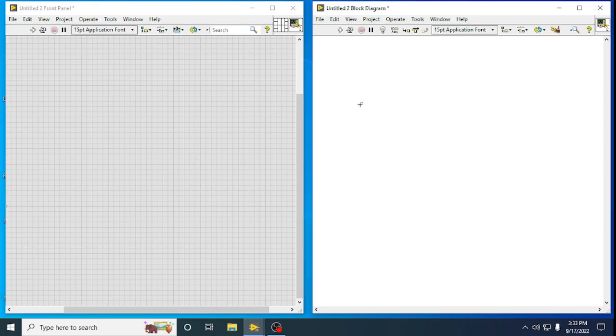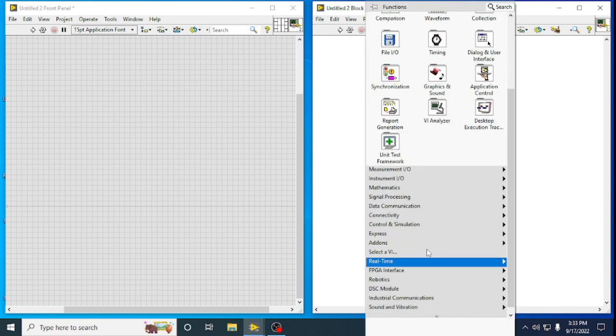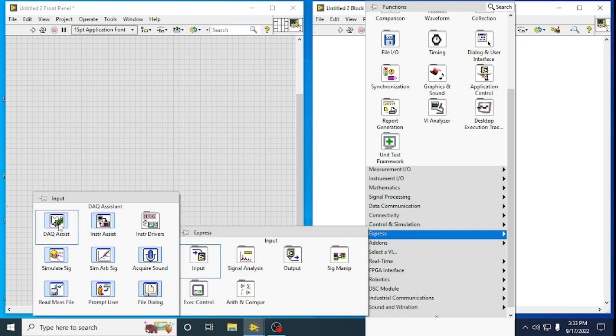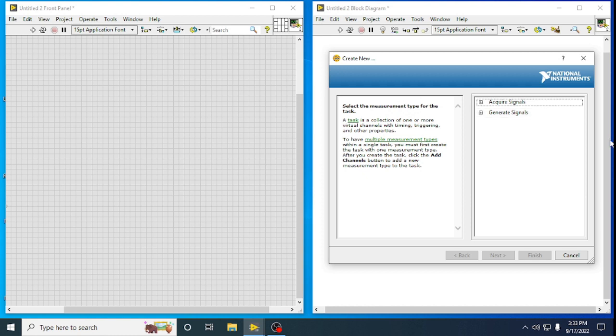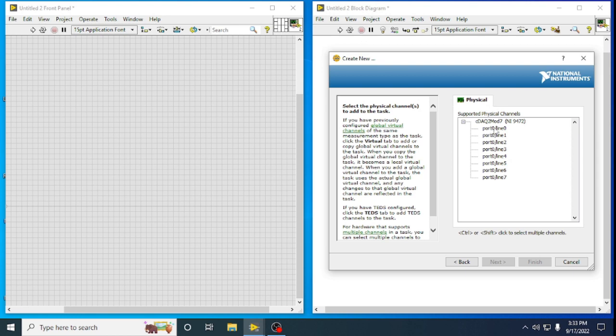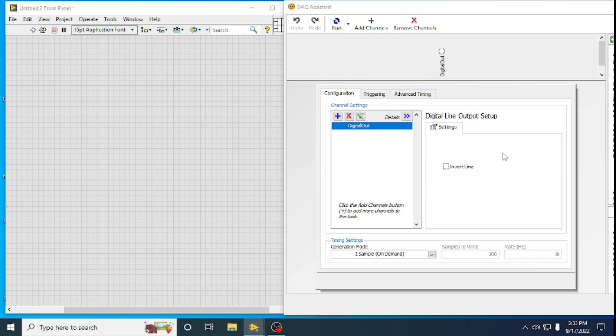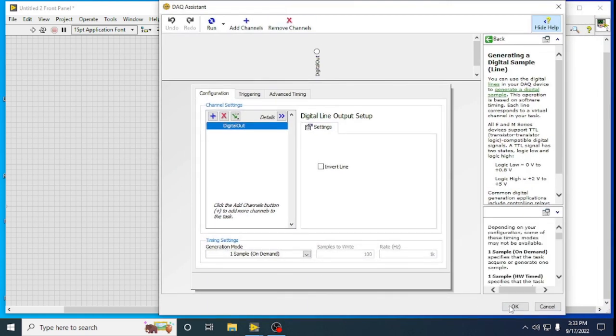Now we are going to see how to acquire and generate a digital signal. For that, take a DAQ Assist again — since we have the hardware connected, go to Input DAQ Assist. We first need to generate the digital signal, so select Generate Signal, then Digital Output, choose Line Output, select Port 0 Line 0, and click Finish. You will be asked what generation mode you need — choose Generate One Sample on Demand and click OK.